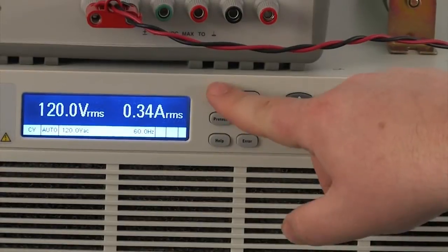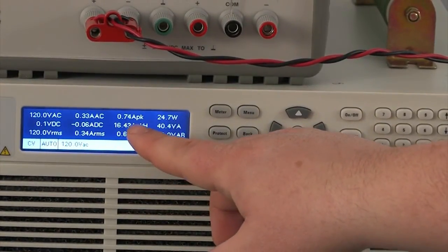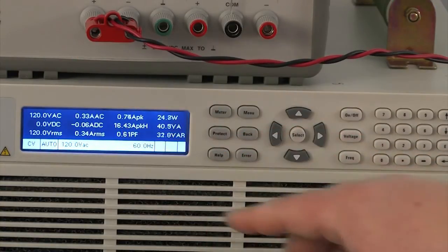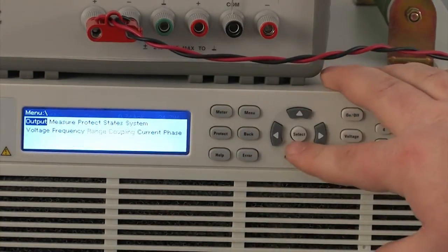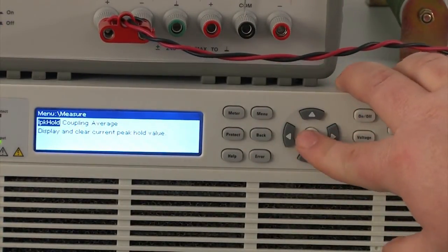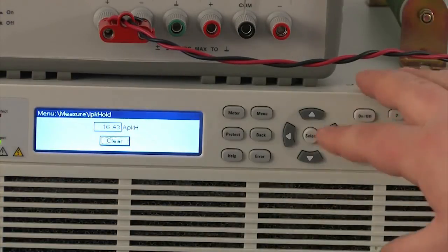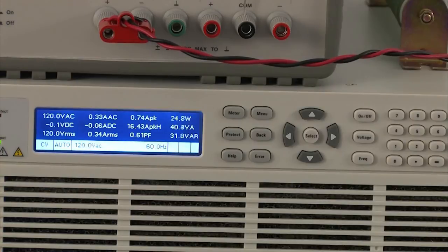So now what we're going to do to get the actual inrush measurement is we're going to hit meter. If you hit meter twice, you could actually go and get the IPK hold right here. So you can see we measured 16.43 amps. You can also go to the measurement menu here and click on this IPK hold and you get the same measurement here.